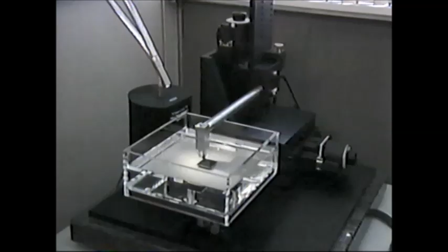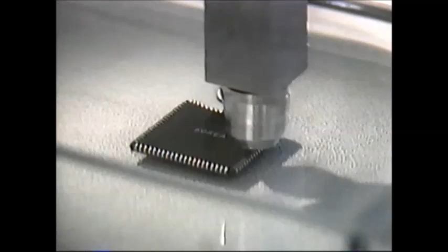One piece of equipment is the acoustic microscope, which is used for examining microchips for packaging problems, such as delamination of the plastic encapsulation of the case. This instrument uses a transducer which focuses, transmits, and receives 25 to 75 megahertz sound waves.